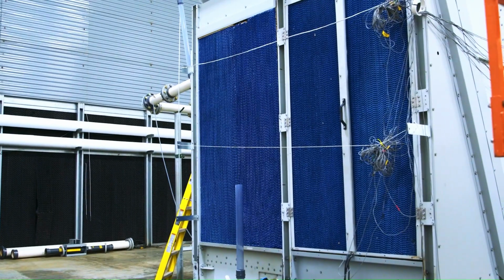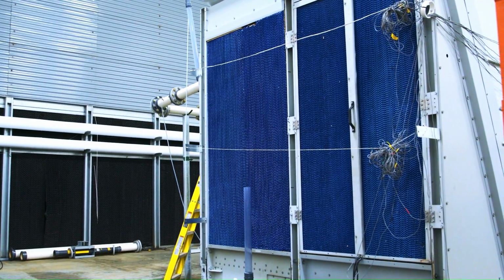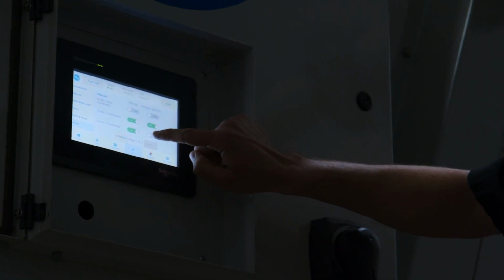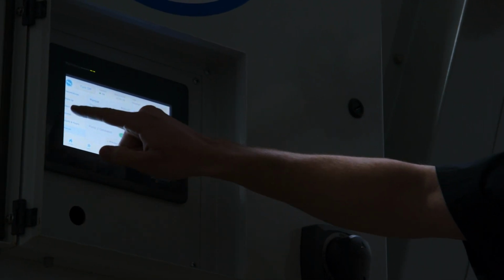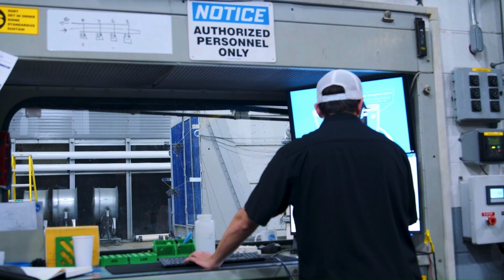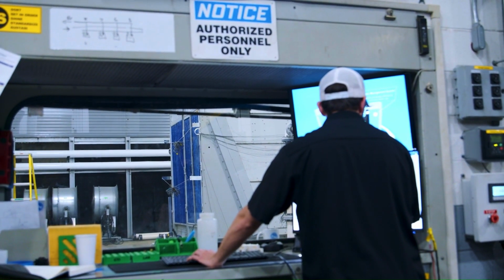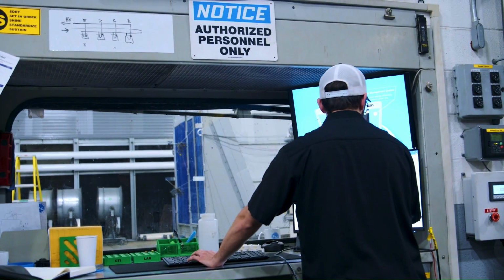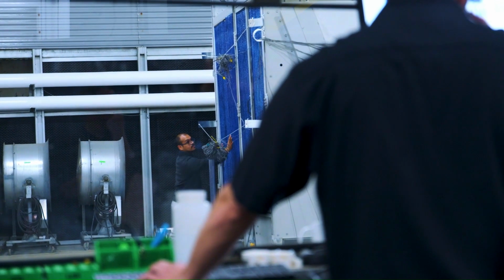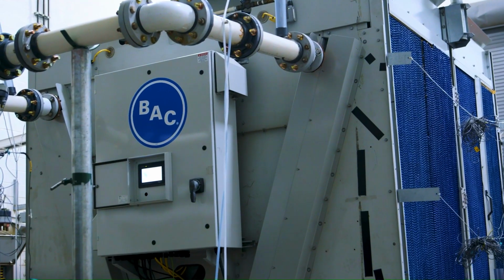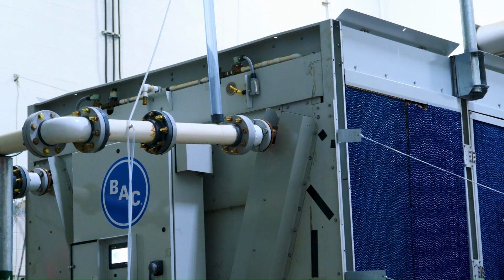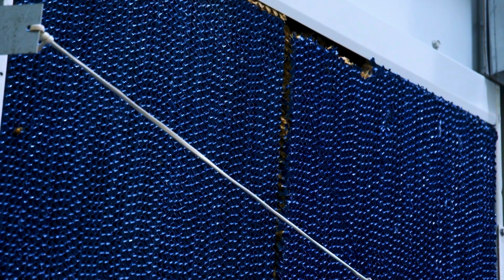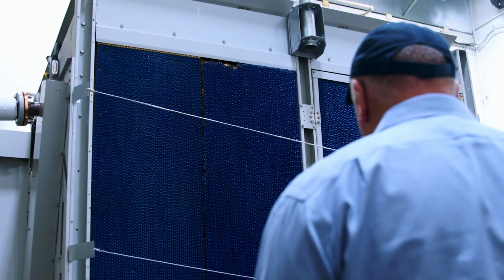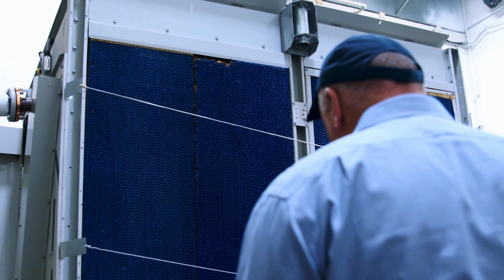As a result, Shumate's novel system design was put to the test. The R&D lab at BAC's world headquarters in Jessup, Maryland, is one of a few in the country capable of recreating extreme ambient temperature and humidity-controlled environments, allowing engineers to evaluate equipment performance under simulated real-world conditions. The goal was clear: evaluate system performance in dry cooling mode under hybrid adiabatic operation during peak summer conditions and across other critical operating scenarios.